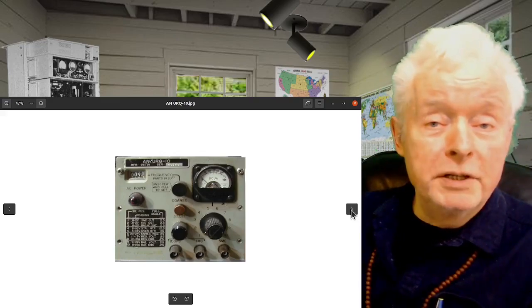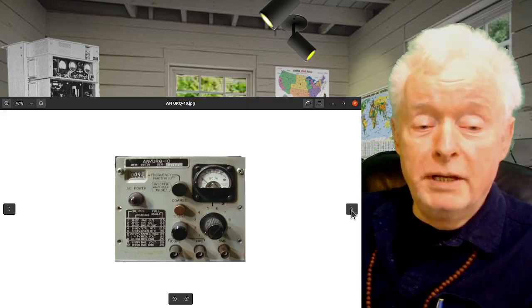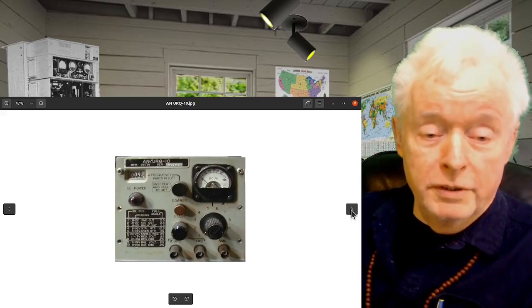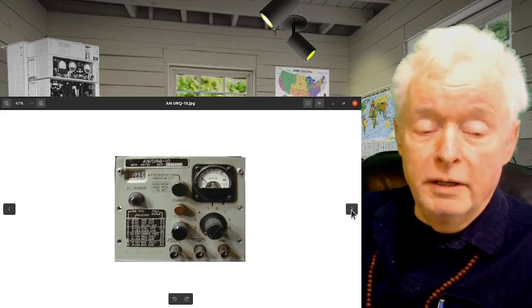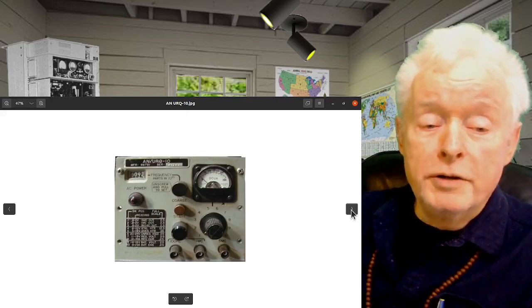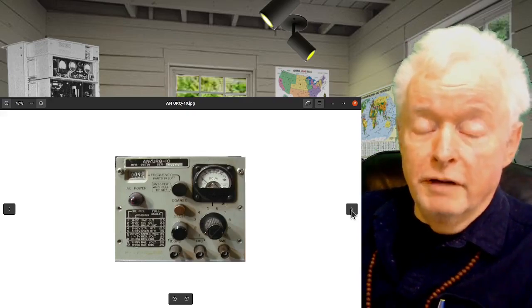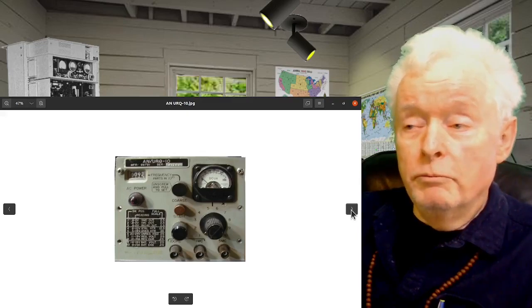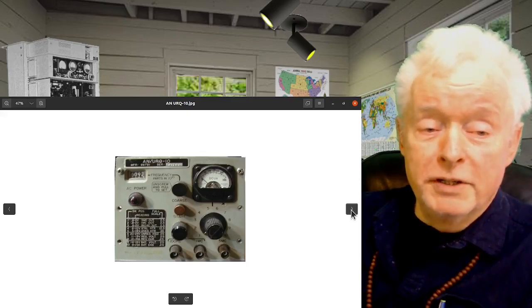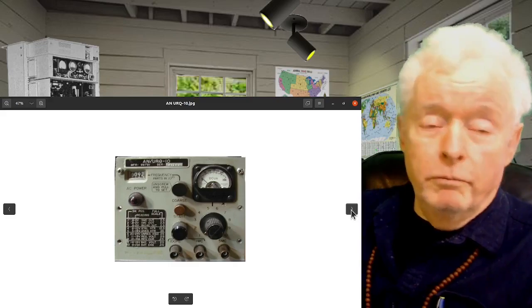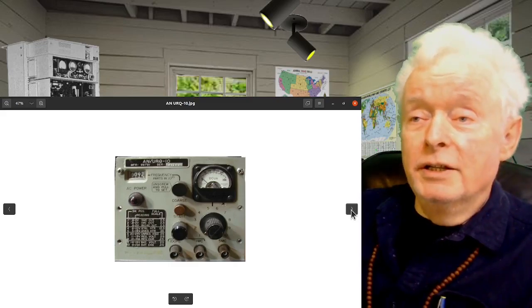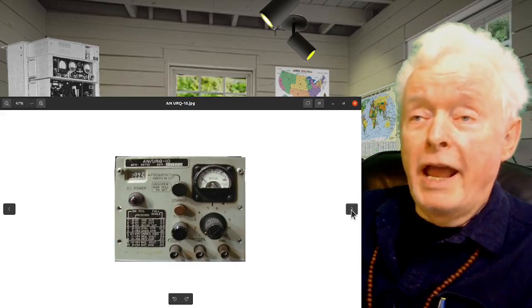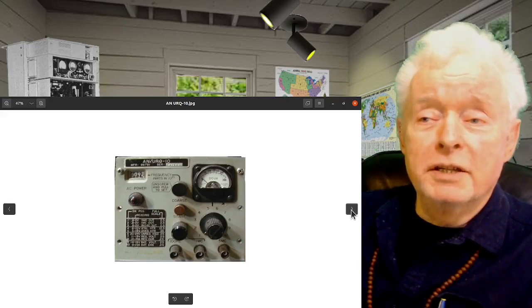Some equipment is suited to accepting it, and if you look at the bottom connectors here, we have a 100 kilohertz, 1 megahertz, and a 5 megahertz frequency emerging from this. That, when it's calibrated, is accurate to 1 part in 10 to the 10th.